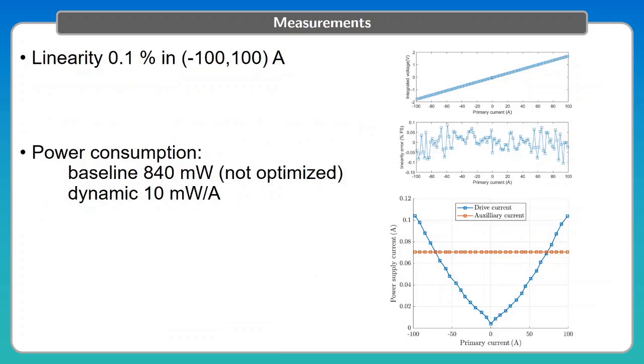These are the results that we get. Linearity is very good, 0.1% between minus 100 and plus 100 A.